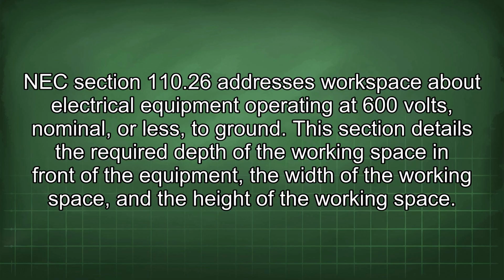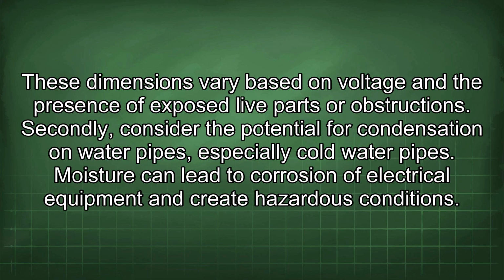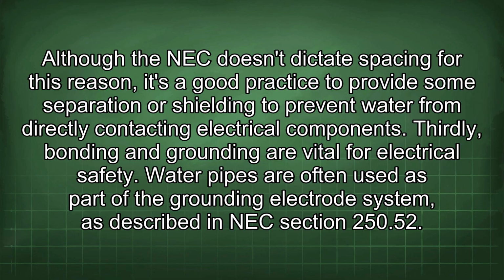This section details the required depth of the working space in front of the equipment, the width of the working space, and the height of the working space. These dimensions vary based on voltage and the presence of exposed live parts or obstructions. Secondly, consider the potential for condensation on water pipes, especially cold water pipes. Moisture can lead to corrosion of electrical equipment and create hazardous conditions. Although the NEC doesn't dictate spacing for this reason, it's a good practice to provide some separation or shielding to prevent water from directly contacting electrical components.